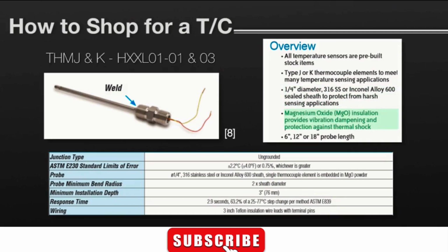The magnesium oxide internal insulation in the probe protects the tiny thermocouple wires from damage during the extreme heating and cooling cycles that the probe undergoes. The ungrounded junction means that the thermocouple wires are not electrically connected to the probe sheath. American Society for Testing and Materials E230, that's ASTM E230, governs the accuracy of thermocouple sensors, which is nominally 0.75% of reading, but at least 2.2 degrees C.